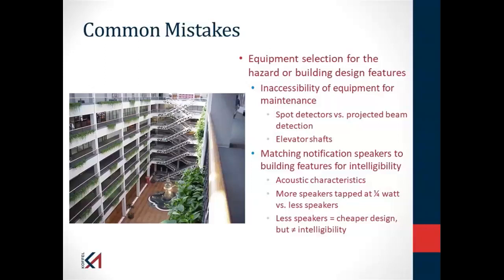It's not convenient. But I could have put projected beam detectors on those walls along the balcony that you see there. Now I can access the projected beam detector from the floor of the balcony, and I can do the required testing.